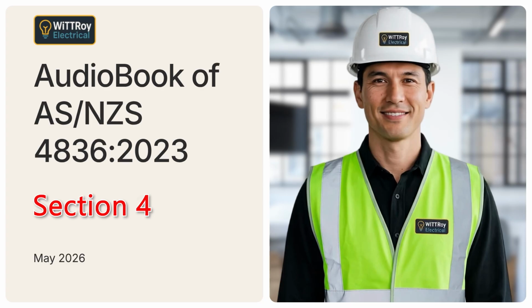Clause 4.3.2 Capacitors. Clause 4.3.2 explains the danger from capacitors. Capacitors can store a large amount of electrical energy. This stored energy may still be present even when the equipment has been de-energized. That stored energy may cause electric shock, electrocution, arcs, flash burns, or ignition of gas or solid material. Before work starts on capacitors or their associated circuit wiring, the capacitors must be proved de-energized and fully discharged. This may be done using suitable discharging devices or by following the instructions for use. The safe discharged condition must be maintained for the duration of the work.